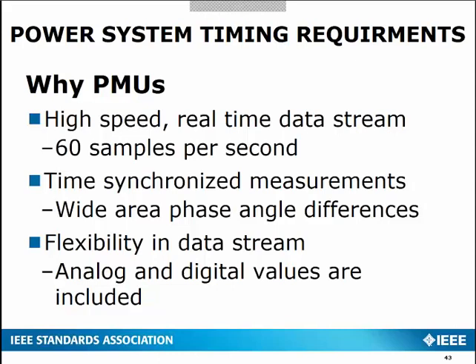So why PMUs? Why do we want to use PMUs? Well, it's a high-speed real-time data stream. 60 samples per second is what we get from our wide area PMUs, and synchronization to combine the data is very important. It also provides flexibility in the data stream. Not only do we get analog values from the data streams, we also get digital values of what's going on in the power grid.